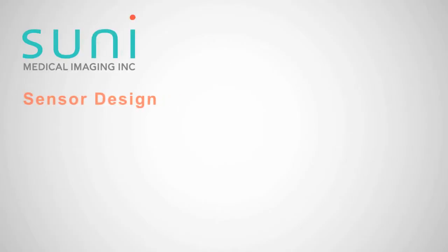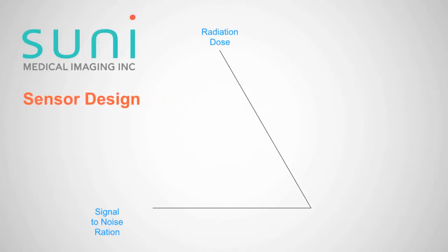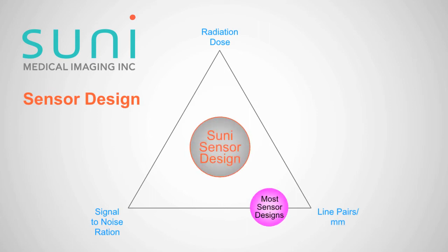The first fundamental relationship is between dose and signal quality — or, in engineering terms, the signal-to-noise ratio — and that goes with a square root function. So to double the signal-to-noise ratio, you have to increase the dose by a factor of four.